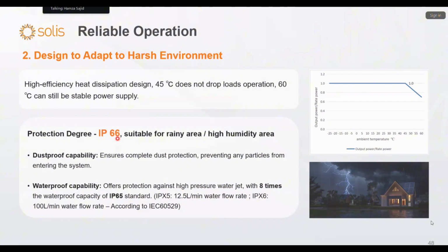High efficiency heat dissipation design: at 45 degrees Celsius, it does not derate the load operation, and at 60 degrees Celsius it can still provide stable power supply. The protection degree is IP66, suitable for rainy areas and high humidity areas like near the sea, where the humidity is very high. So the inverter has dust proof and waterproof capability. IP66 offers protection against high pressure water jets, with 8 times the waterproof capacity of IP65. Like a power jet, if you throw a water jet, the power that IP66 withstands is 8 times higher than IP65.